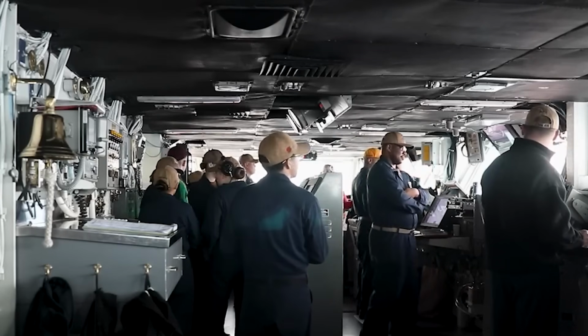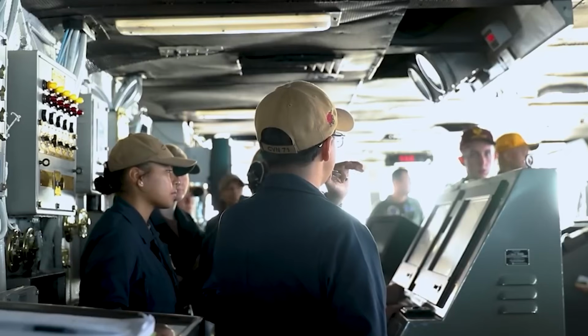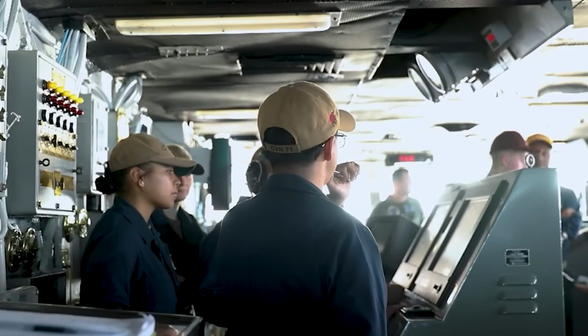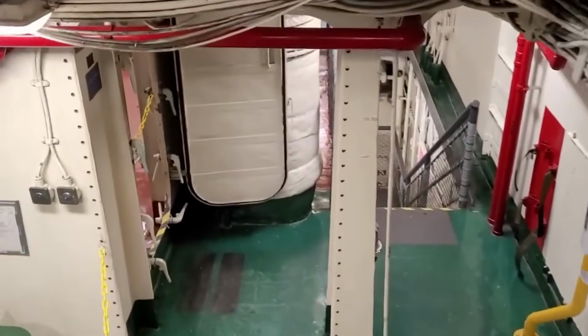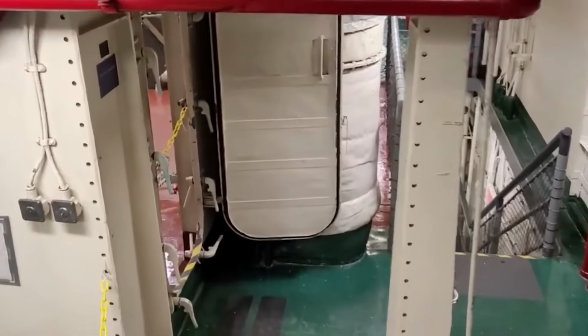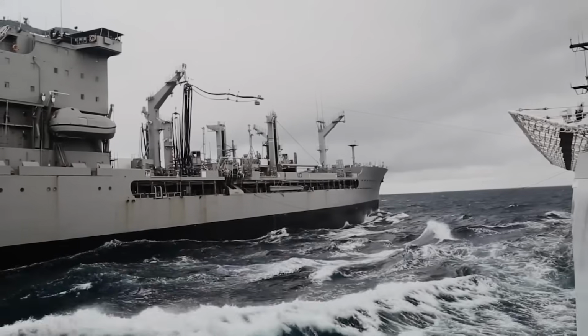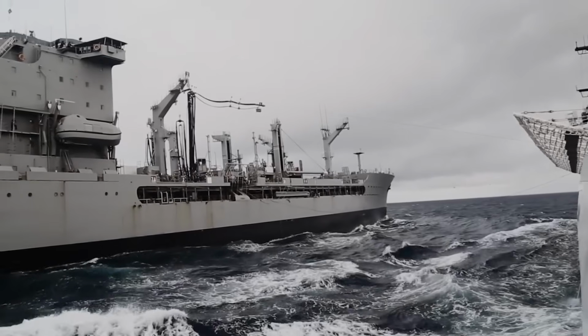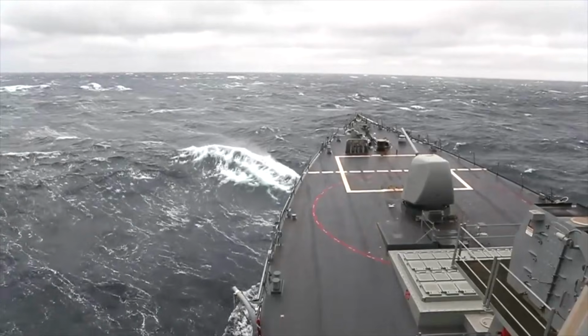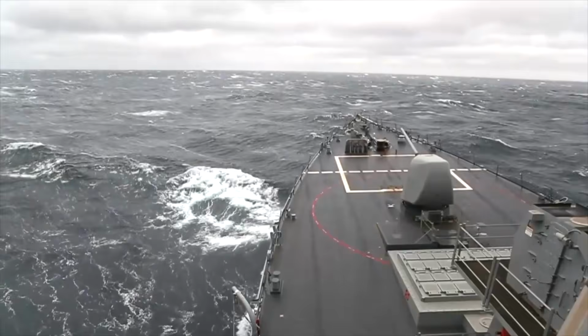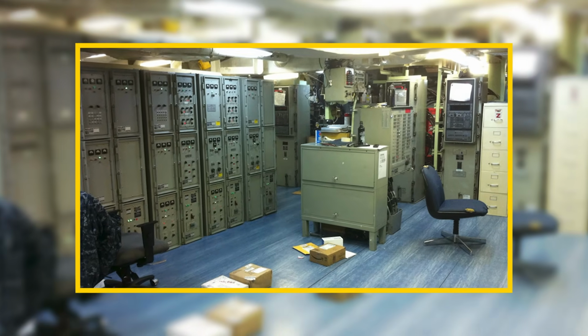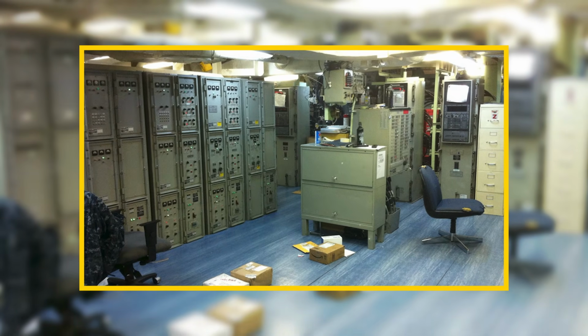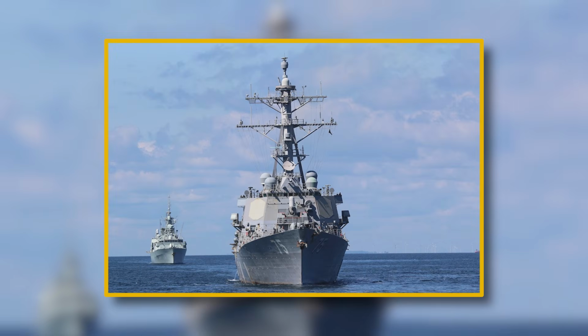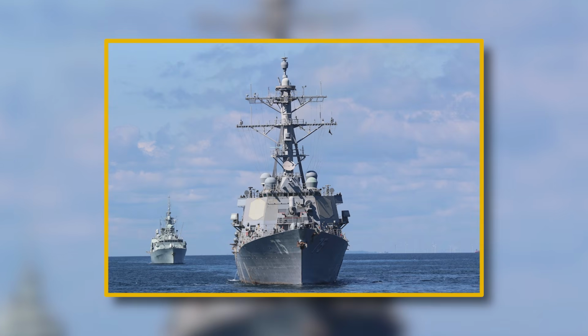So the crew isolates. Valves shut. Breakers open. Tags go on. Logs update. Then a second set of eyes verifies. You prove the system is dead before hands go in. Now, the downstream check. If you secure this pump, what else loses cooling? If you shut this valve, what else did you just starve? Chilled water sounds like comfort until you remember it may be cooling combat systems cabinets. Which is worse, the initial failure or the secondary casualty you create by skipping isolation?